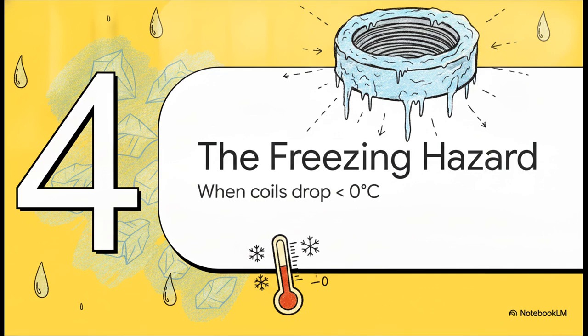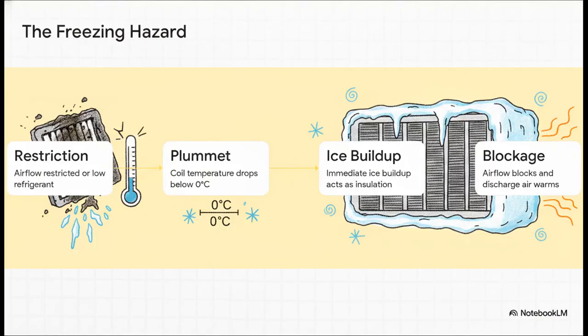Which brings us to part 4, the freezing hazard. This is what happens when those coils drop below 0 degrees Celsius. This step-by-step chain reaction shows the freezing hazard, and it's a huge deal. If your system is trying to maintain that 16-degree discharge, but the internal coil drops below freezing, you have a severe problem. Step 1 usually starts with restricted airflow. We're talking dirty air filters, blocked vents, or a failing blower motor preventing warm air from hitting the coil. Or it could be a low refrigerant charge, where a tiny leak causes the remaining refrigerant to overexpand.